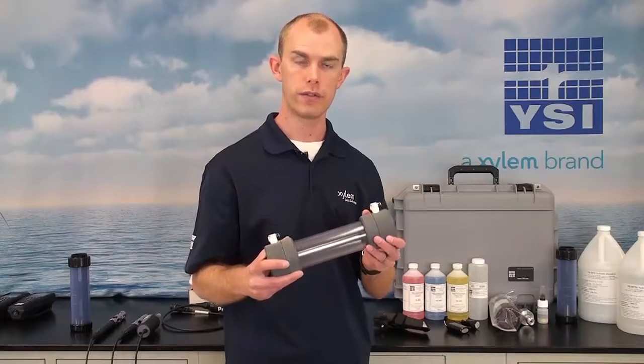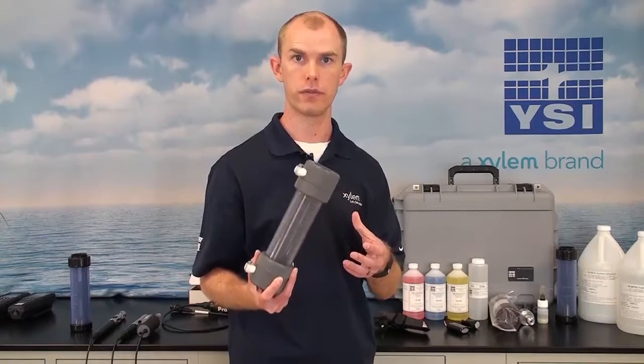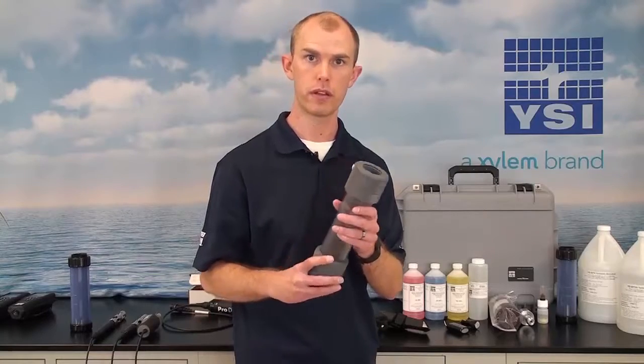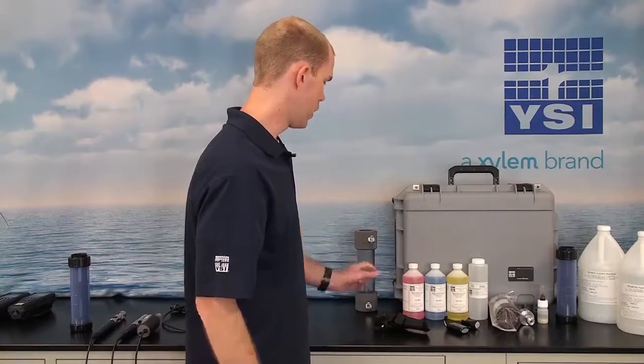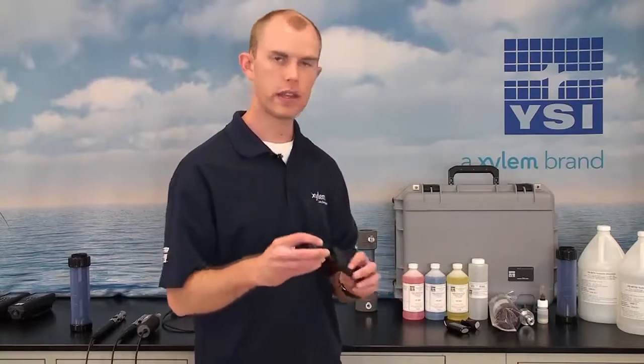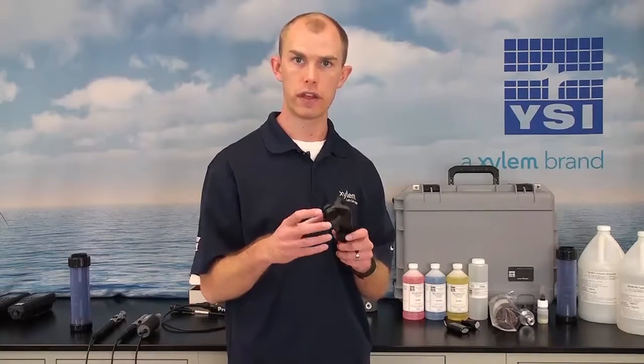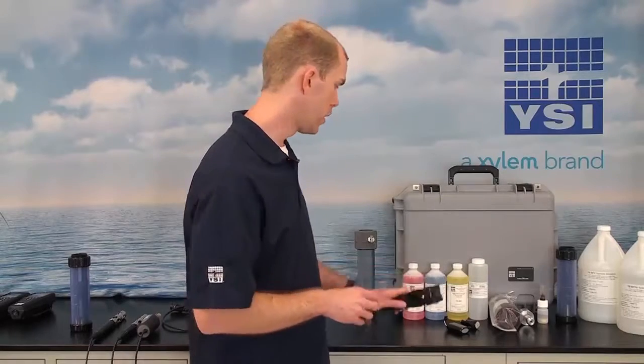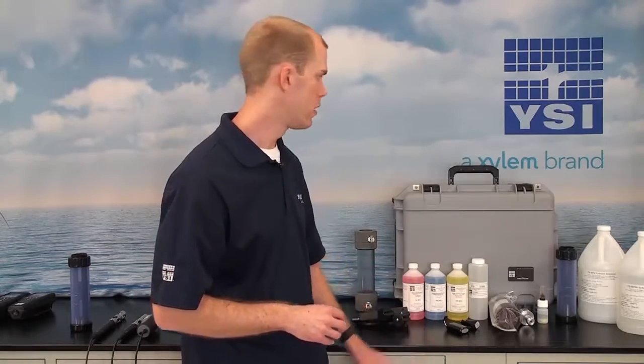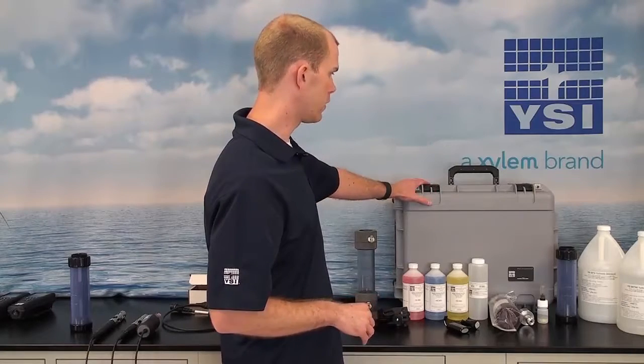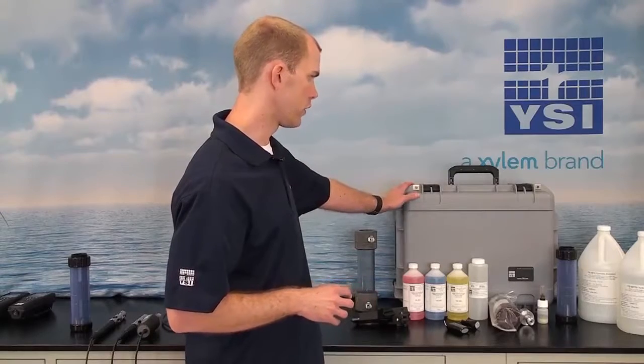Some other accessories that we have, if you are doing any sort of groundwater investigation, we do have flow cells that are available that the ProDSS bulkhead and sensors will fit into. This is for a 4-port sensor or 4-port cable. We have a tripod that screws into the back of the handheld, and this can be used to prop up the handheld on a bench top. We have some different cases that are available. This is the large hard-sided case, and it has space to fit not only the handheld but also a 30-meter, 4-port cable with the bulkhead as well. So that is the large hard-sided case.